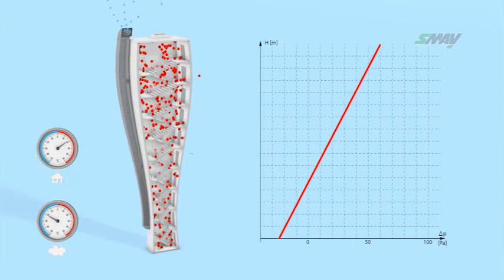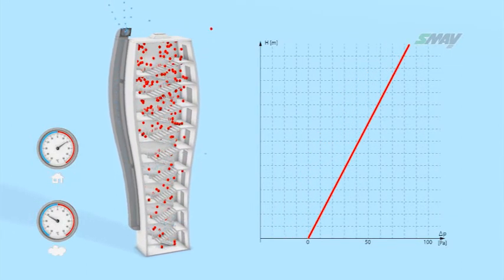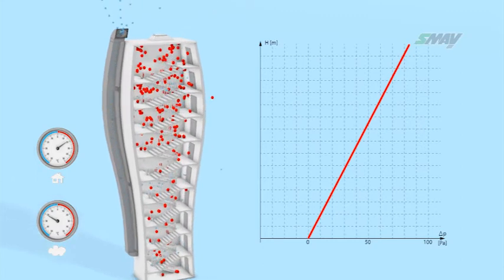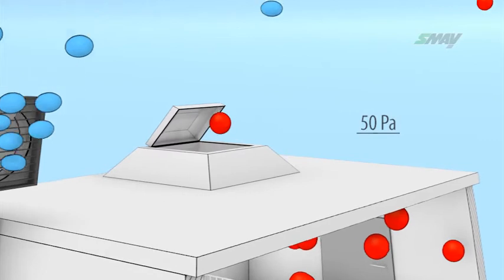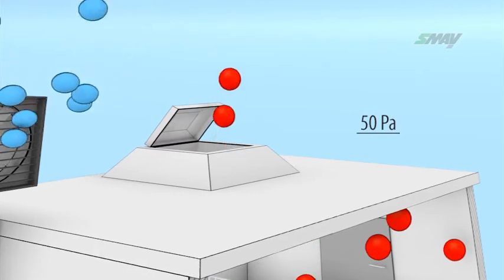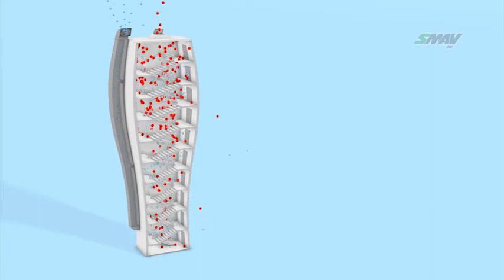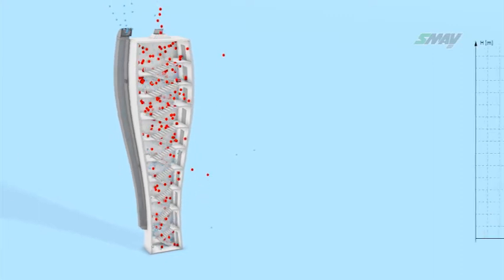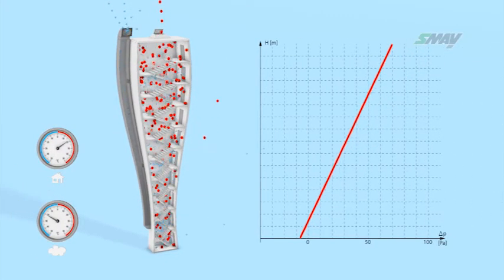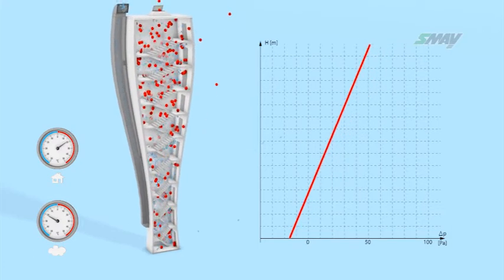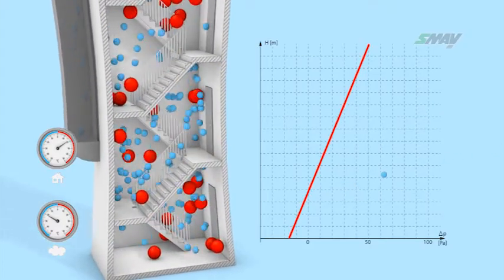Consequently, air pressure rises in the upper parts of the stairwell. The excessive pressure rise in the upper parts causes the barometric overpressure dampers to open, doing their job of maintaining pressure at no more than 50 pascal. The cutoff dampers only restrict pressure locally in the upper parts of the stairwell, and overpressure in the remaining parts is not controlled in any way and may fall to below the required minimum.